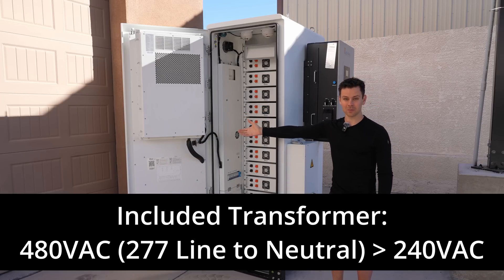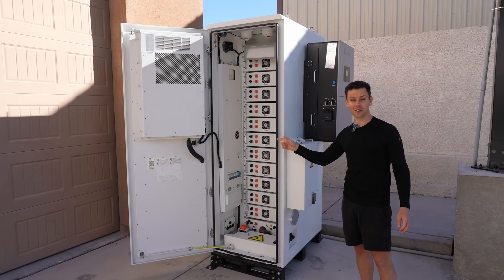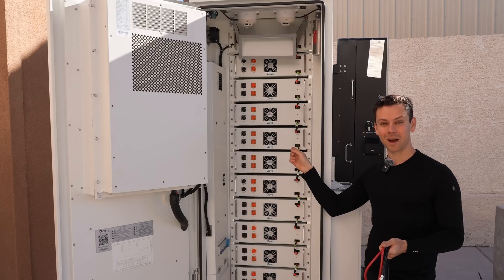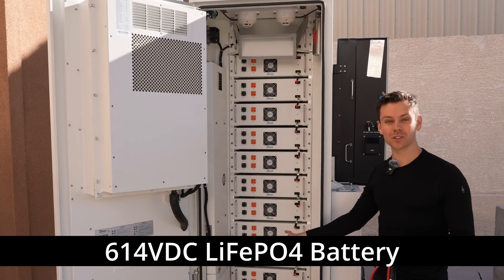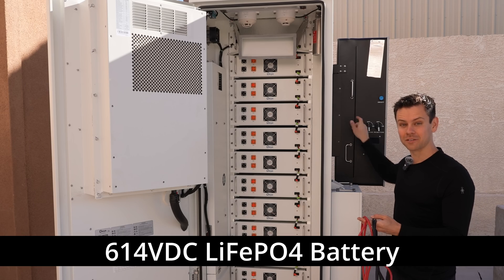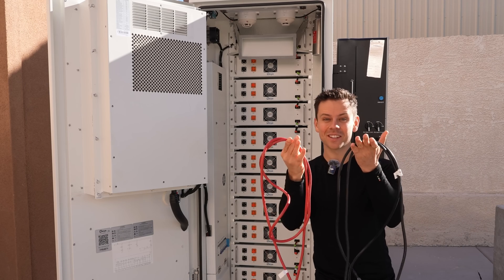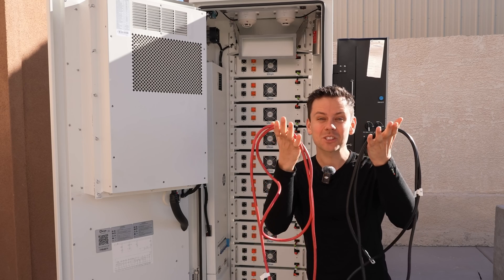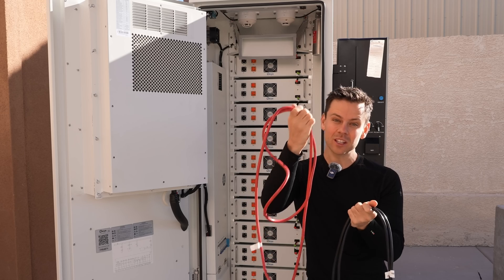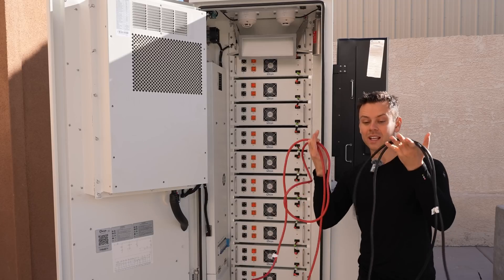This battery is pretty crazy. It's a high voltage battery, so all these modules are connected in series. These are the cables that connect them to the SolArk inverter — notice how small they are. Because it's high voltage the current is low, so we can use small cables. We'll connect this first before connecting the modules in series, because this is super dangerous.